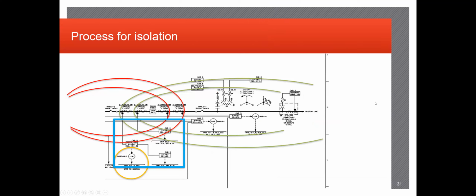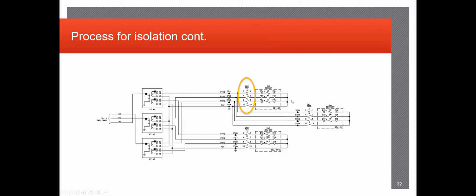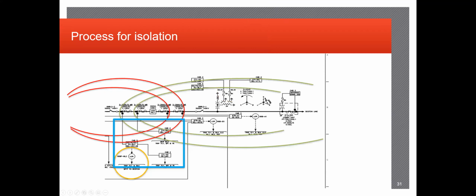Going into the process of isolation, this is a big portion for the start of an outage. We have to identify what equipment is being taken out of service, in what order, and how we're going to go about doing that. For example, let's say we're going to remove this breaker out of service from this string. The first thing we'll probably want to do is open the breaker itself, and that will break the string of circuit here on this bus work.